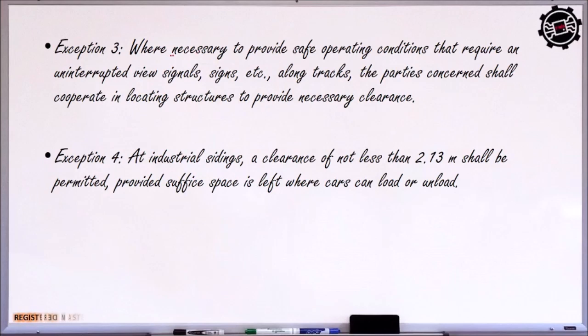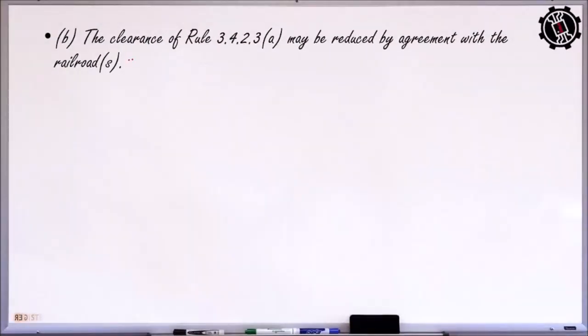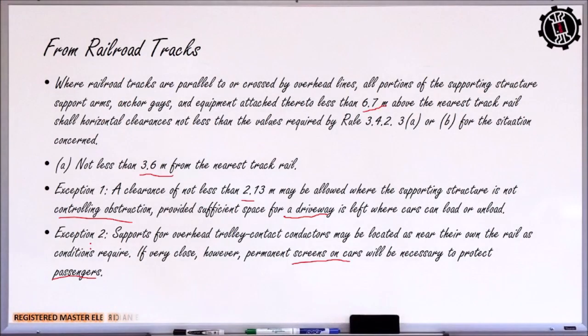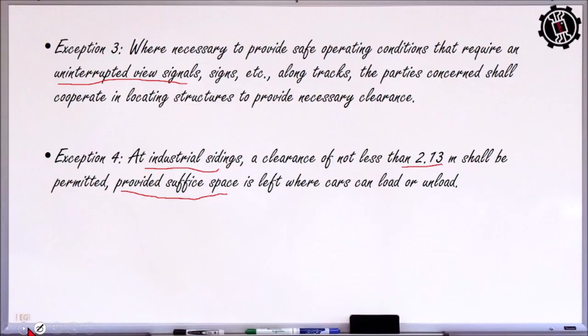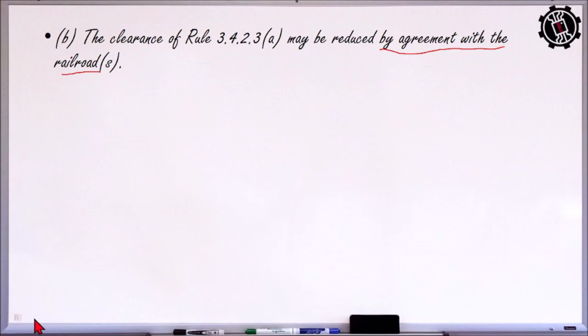So exception naman 3, no, where necessary to provide safe operating conditions that require uninterrupted view of signals. So yung ating equipment ilalagay naman natin not to obstruct the viewing of the signal ng mag-ooperate ng tren, no? And at industrial sidings, a clearance of not less than 2.13 meters shall be permitted, provided mayroon siyang space left where cars can load or unload. Okay. So the clearance of Rule 3.4.2.3a may be reduced by agreement with the railroads. So itong lahat ng ito, pwede siyang ma-reduce as long as there is an agreement between the utility company and the railroad operator or the railroad company.